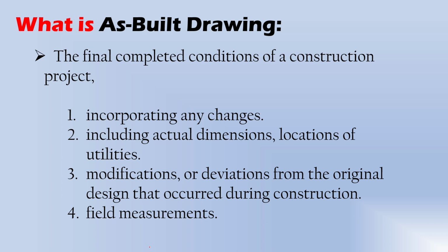So you have a shop drawing approved, you follow it in the site work. And due to the site condition, you may change something at the site. The shop drawing and site condition are different. You have made some changes. Those changes should be included in the as-built drawing. If those changes happen, automatically the dimension will also change, and the location will somehow change.